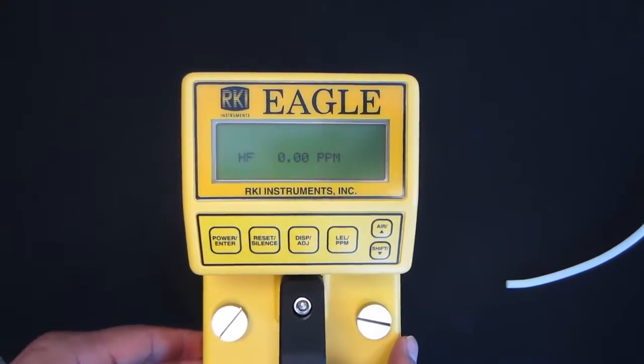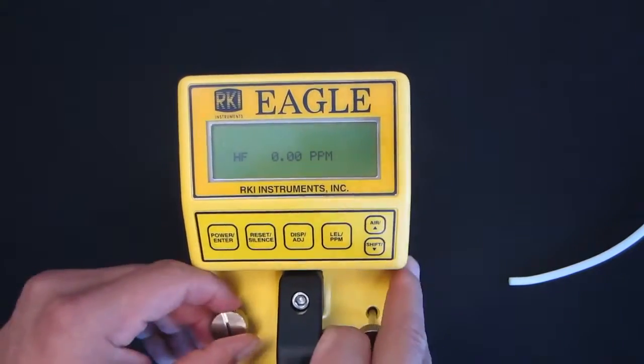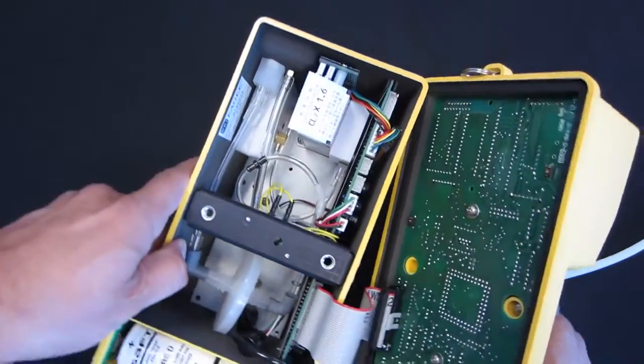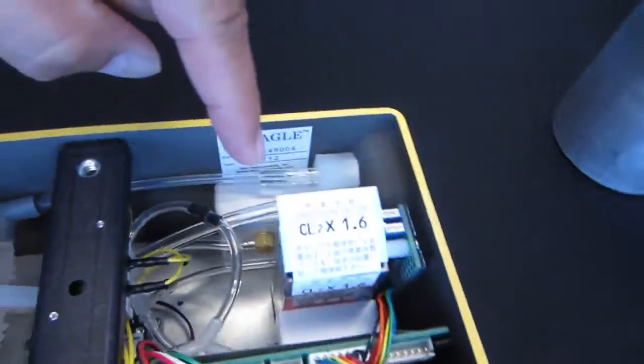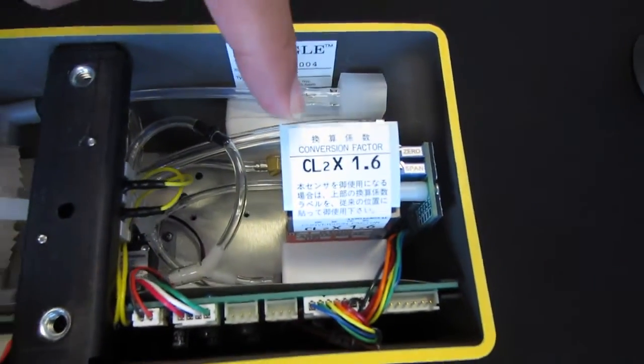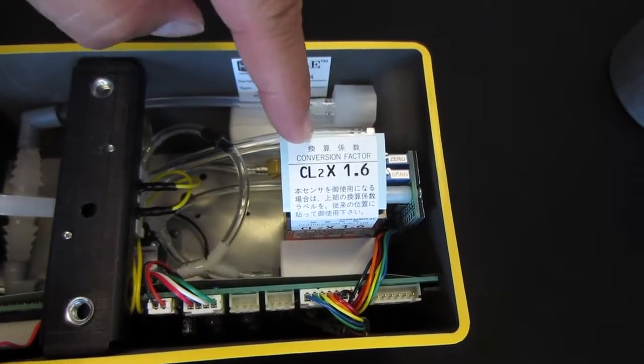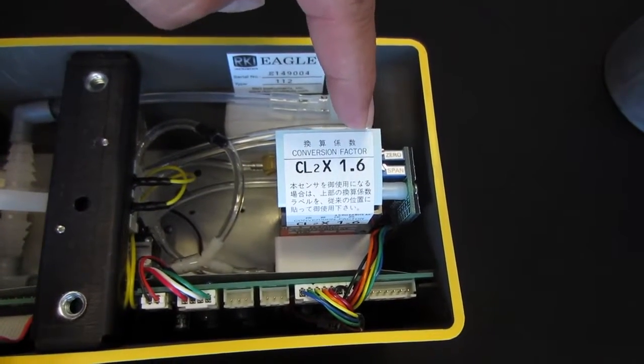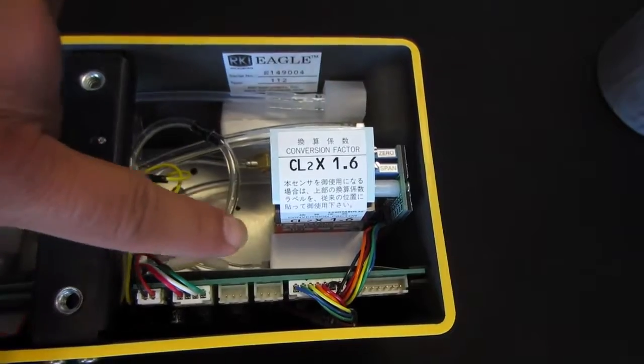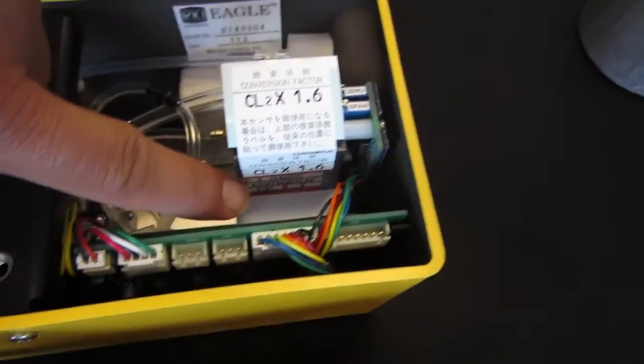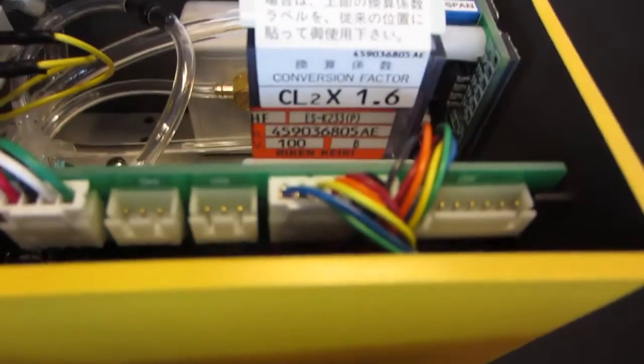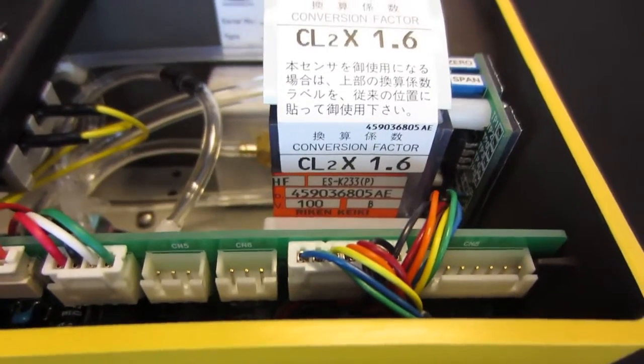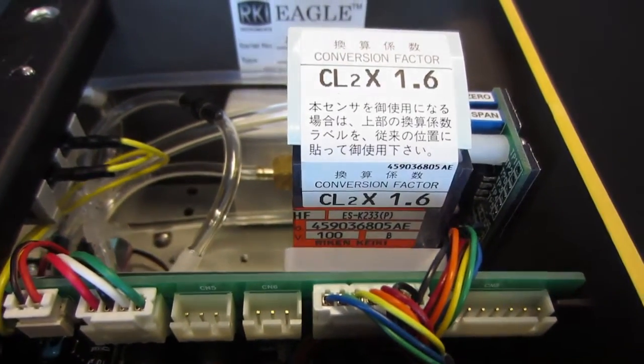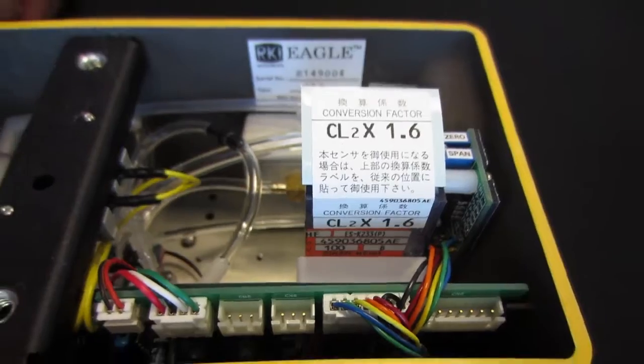And if I open the top of the instrument, we can see the sensor here, and in fact there's a label that states that Cl2 chlorine times 1.6 equals HF. There is a little HF designation for the sensor itself. So basically, we're using 5 ppm of chlorine today, and times 1.6 is going to give us 8 ppm.